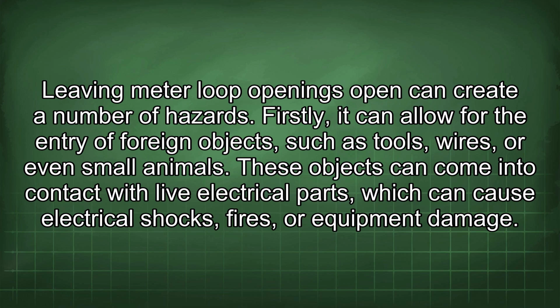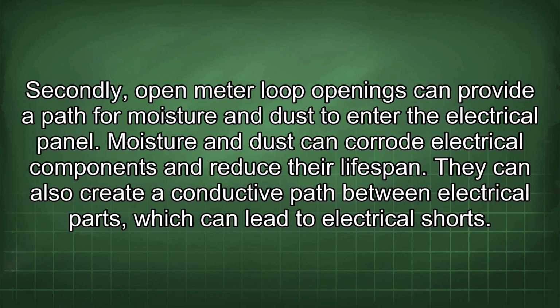Firstly, it can allow for the entry of foreign objects such as tools, wires, or even small animals. These objects can come into contact with live electrical parts, which can cause electrical shocks, fires, or equipment damage. Secondly, open meter loop openings can provide a path for moisture and dust to enter the electrical panel.